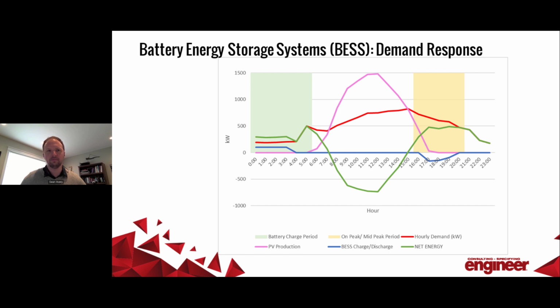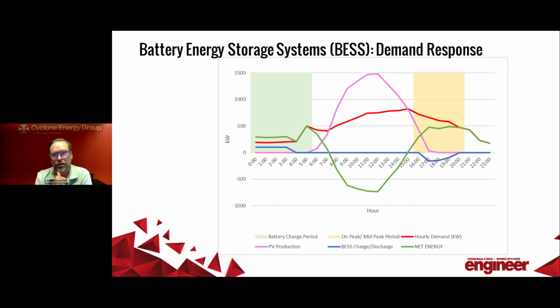And Sean, when looking at zero energy buildings and sizing these arrays, you have to understand what those loads after hours are too. A lot of buildings, when you get into the commercial realm, aren't necessarily 9 to 5. You might have a refrigerated facility, or something with 24-hour operations, like a data center or mission critical facility. To size those for zero energy, you have to have significant overproduction during peak hours to handle not just the shifts at evening and morning, but also overnight.